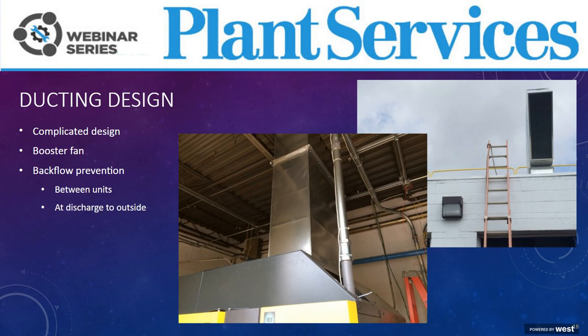It may not look like there's a lot going on with this particular picture, the one on the left and the one on the right. It's the same duct, if you would, but let me break it down for you a little bit. First, the duct was sized exactly to the cooling air discharge of the machine, so that's what we said was kind of a no-no, if you would.